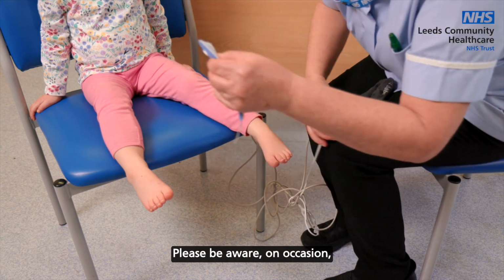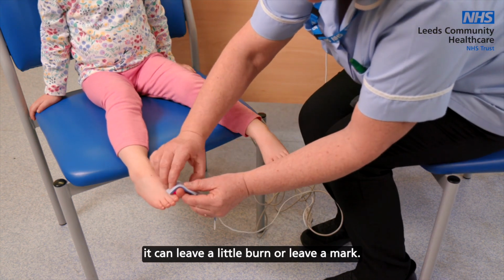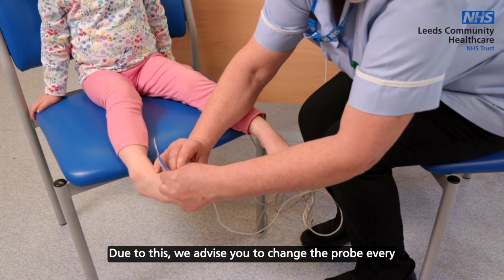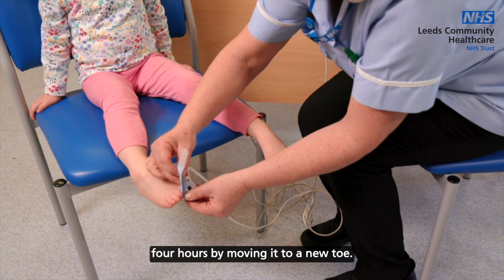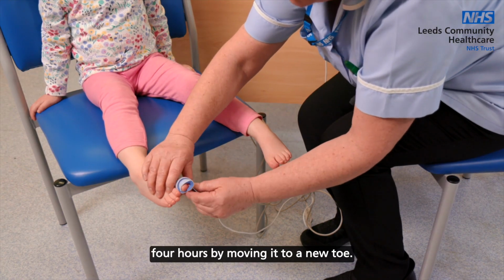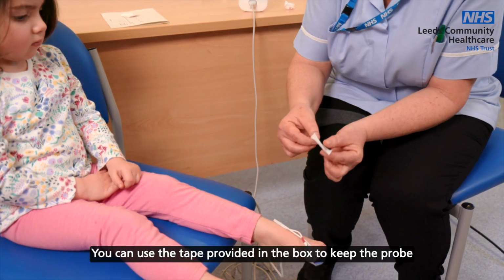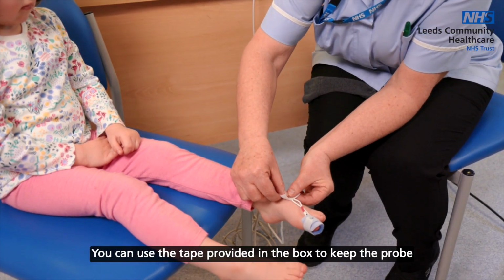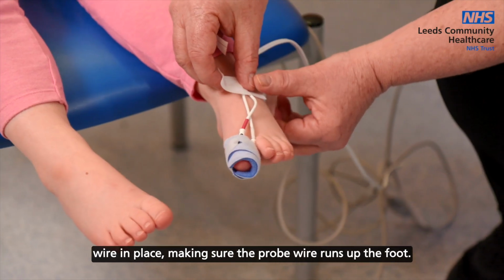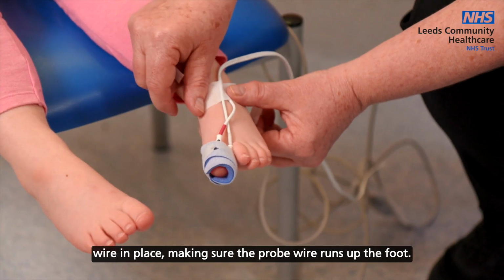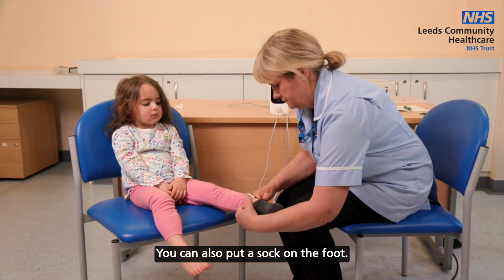Please be aware on occasion it can leave a little burn or leave a mark. Due to this, we advise you to change the probe every 4 hours by moving it to a new toe. You can use the tape provided in the box to keep the probe wire in place, making sure the probe wire runs up the foot. You can also put a sock on the foot.